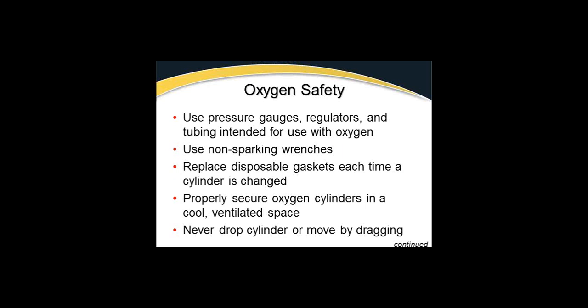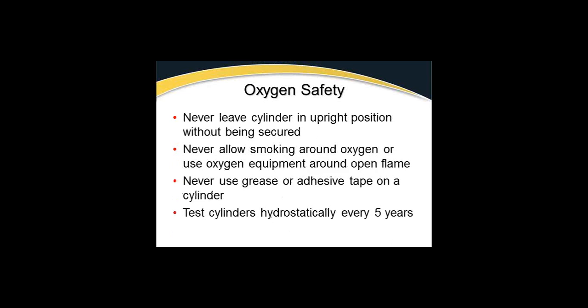Properly secure the cylinder in a cool, vented space so it's not rolling around. Never drop a cylinder or move it by dragging, as you'll weaken the cylinder. And never leave it upright without being secured. Technically, it should be secured in some very specific manners.